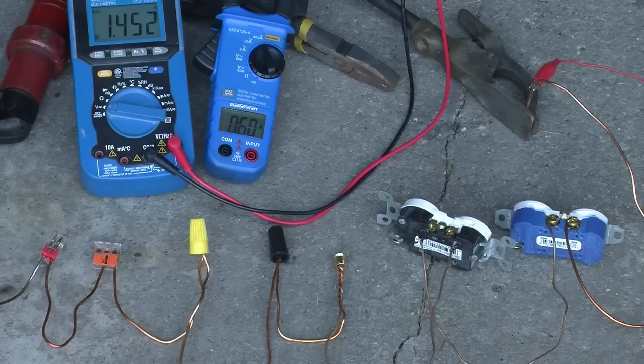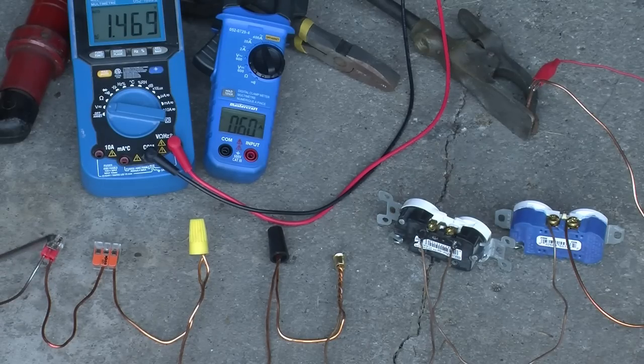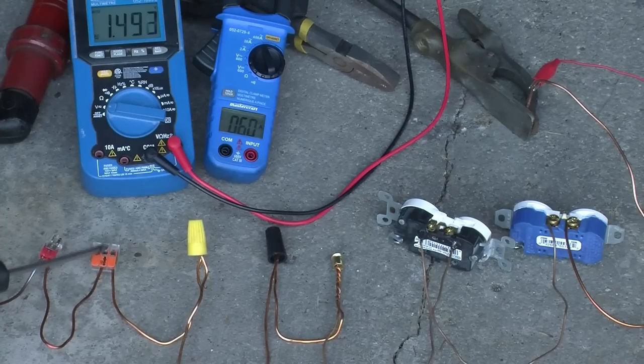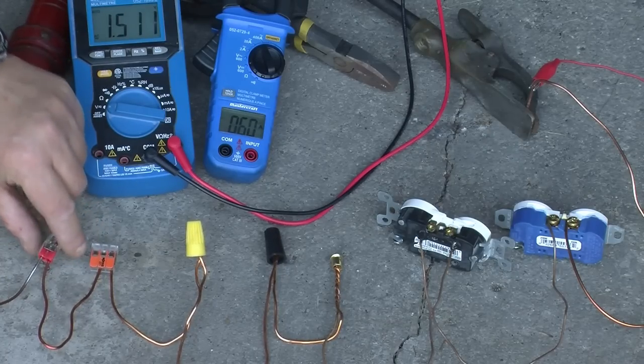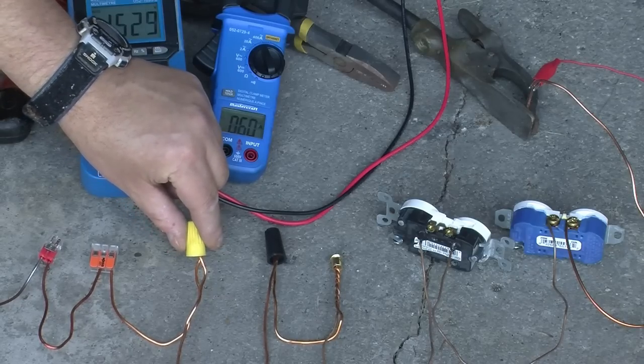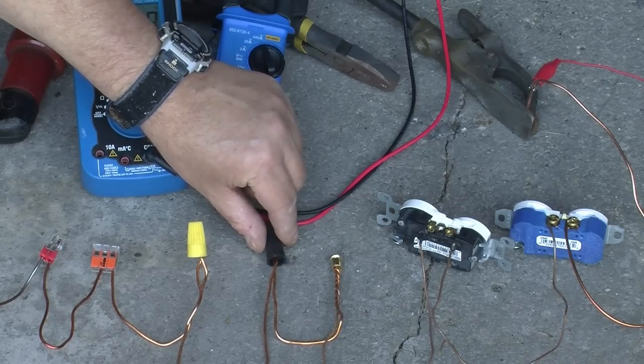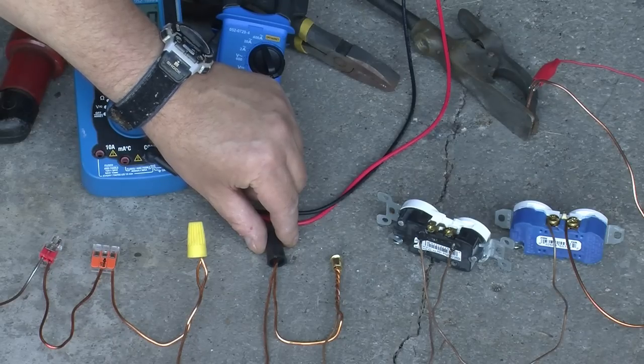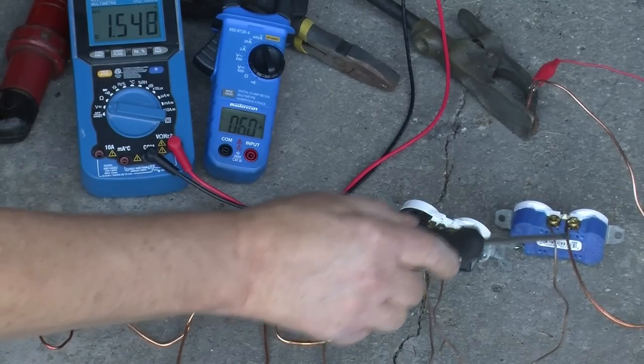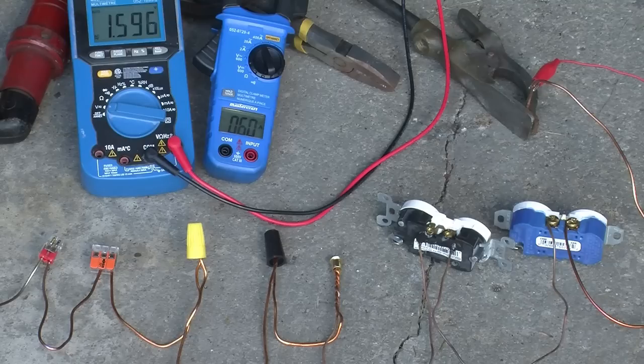This looks awfully hot around here. These two wires are discoloring. It sort of would indicate that it's getting pretty hot in here. How are these connections? Hot. Hot. Amazingly cool. I could touch this for any length of time. Uncomfortable, but I also could touch it for any length of time. I'm not going to even try and touch that or that. How's this plastic? In very good shape. Well, let's crank it up to 65.